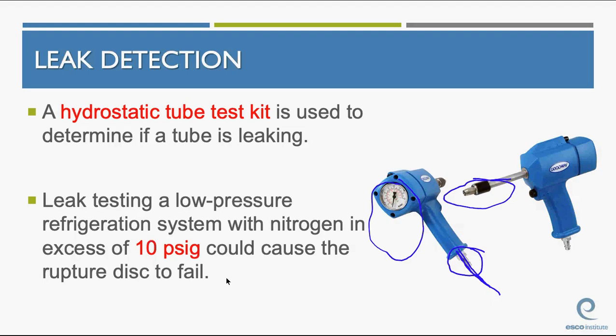Leak testing a low-pressure refrigeration system with nitrogen in excess of 10 psi can cause the rupture disc to fail. Now, we haven't talked about what a rupture disc is yet. A rupture disc is another component on a low-pressure system. It basically replaces a pressure relief valve. A rupture disc is found on the evaporator of a low-pressure system. It makes sure the pressures do not go in excess of a certain psi. Okay, and make sure we don't overpressurize that system. Once a rupture disc fails, it releases all the refrigerant in the system to the air. They have to be replaced. They're not manually resettable. They have to be replaced.